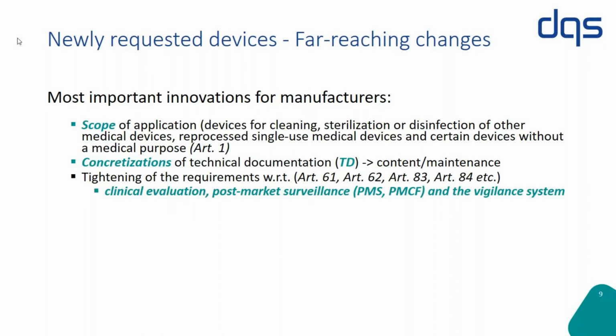We have, and this is the part with the highest impact, I would say, the clinical evaluation, the clinical data, the surveillance and vigilance system. The thing with the European Medical Device Regulation is that the safety of the patient is in focus. So therefore, the requirements are higher with respect to the clinical evaluation. You will see this in reports, in surveillance activities, and so on.